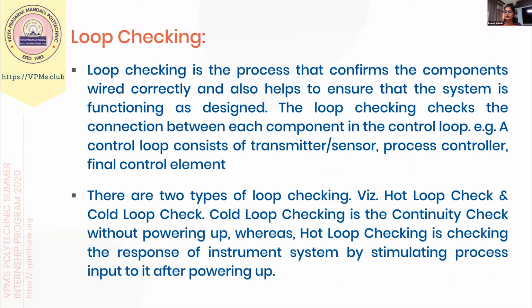So what is the difference between cold loop and hot loop? Cold loop is just a continuity check without powering up, so that we can check the instruments are connected in the right way. Hot loop check is done after powering up the instrument. It is to check the response of the instrument system by stimulating input to the process, like input to the instrument. So that is known as a hot loop check.